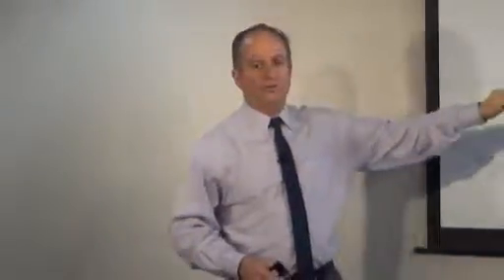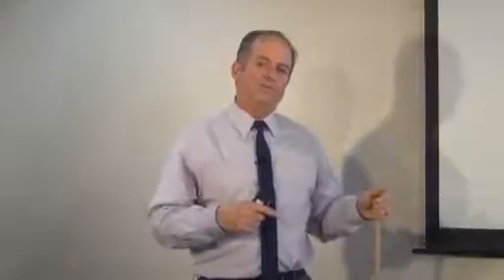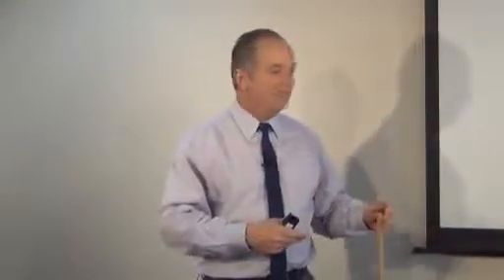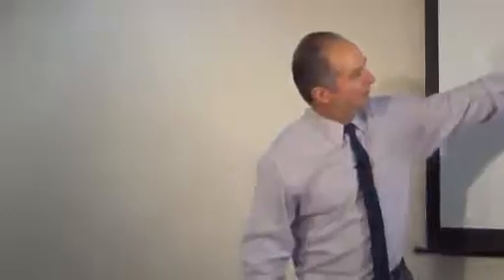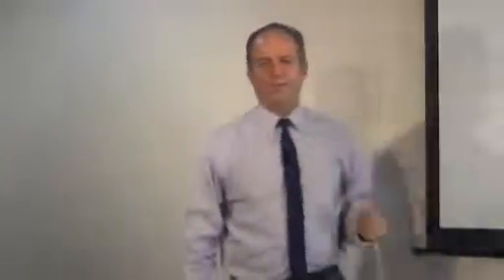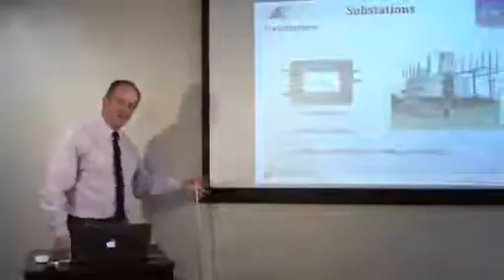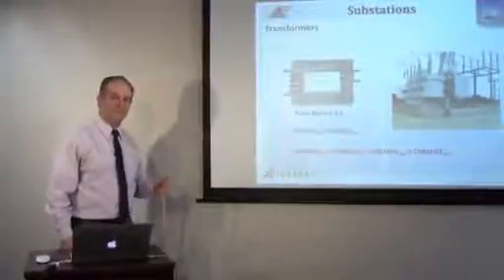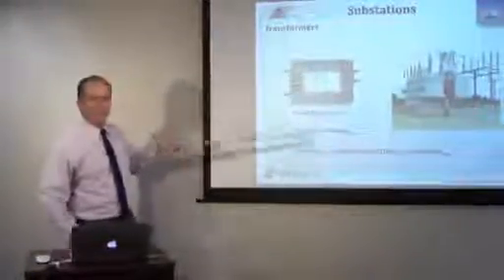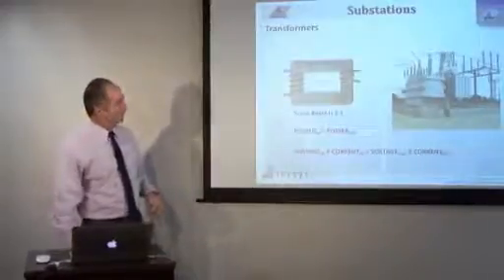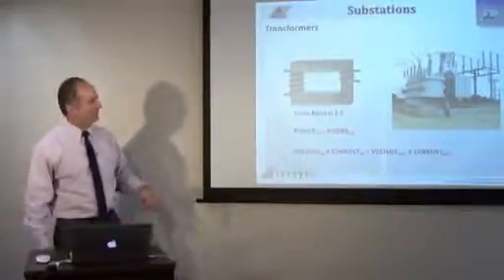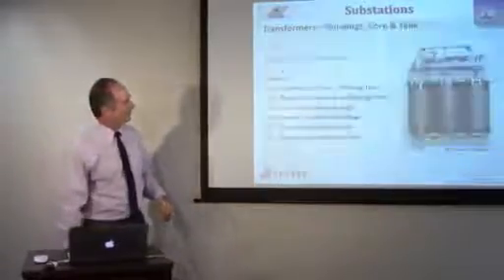And I want you to notice too, remember the low voltage side of a transformer is high current. Notice how many conductors are on the low voltage bushing. There are 3 conductors per phase on the low voltage, yet on the high voltage there's only 1 conductor per phase, because it's high voltage, low current. So you only need 1 conductor. And on the low voltage, high current side, you need 3 conductors to handle that much current. So that's what happens in a transformer. Just the basics, the fundamentals of a transformer. There's a lot more to learn about them, ratings and emergency ratings and things like that.